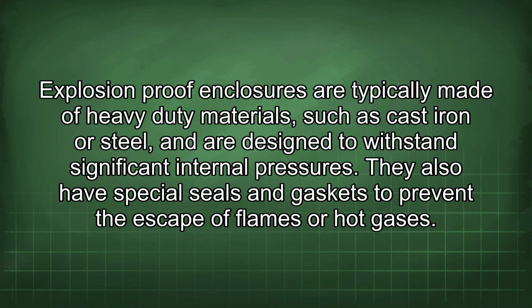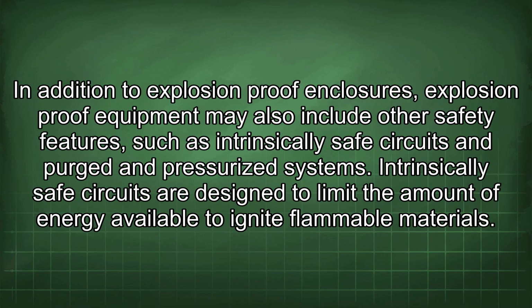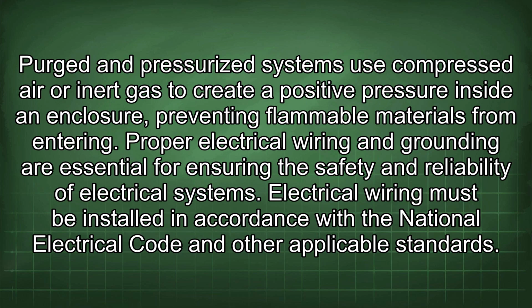They also have special seals and gaskets to prevent the escape of flames or hot gases. In addition to explosion-proof enclosures, explosion-proof equipment may also include other safety features, such as intrinsically safe circuits and purged and pressurized systems. Intrinsically safe circuits are designed to limit the amount of energy available to ignite flammable materials. Purged and pressurized systems use compressed air or inert gas to create a positive pressure inside an enclosure, preventing flammable materials from entering. Proper electrical wiring and grounding are essential for ensuring the safety and reliability of electrical systems.